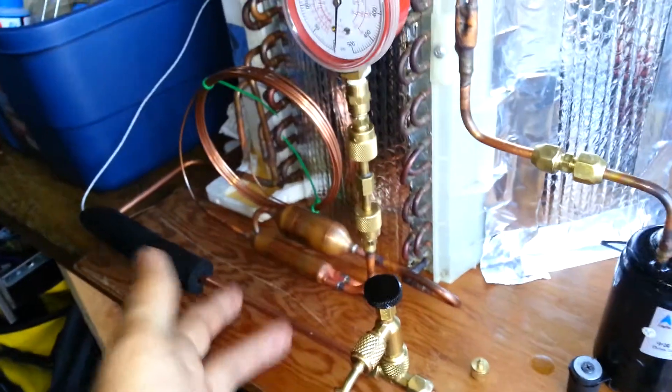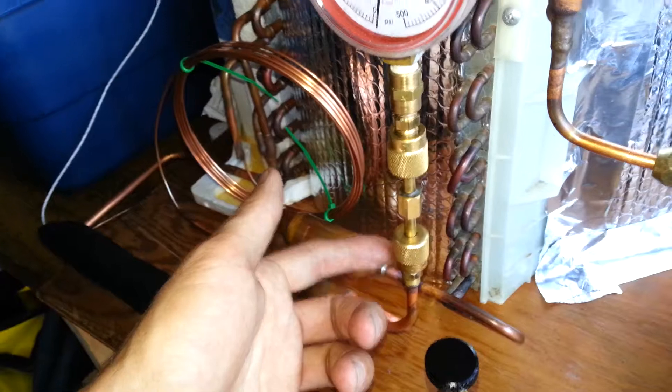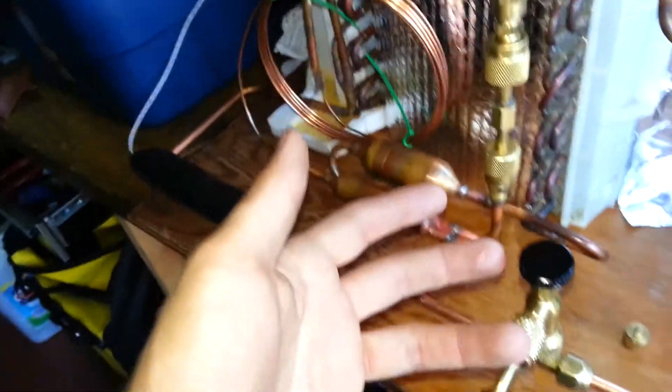But I don't have an actual service port on the high side. It's taken up by this high side gauge right now. So I ought to put a T or something like that in there so I can distribute the vacuum pump to both the high and the low side.